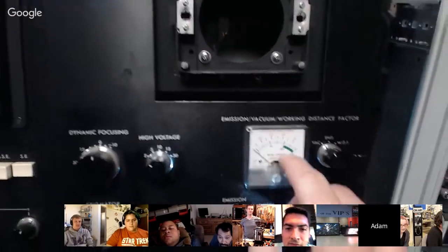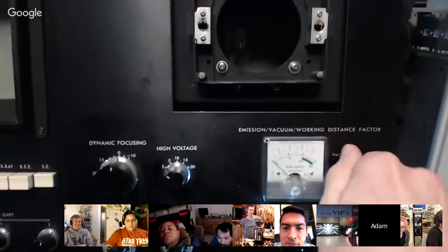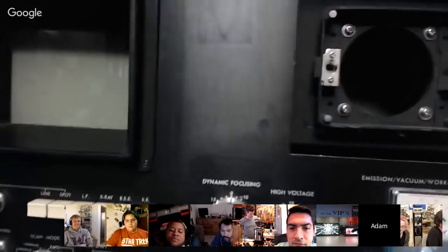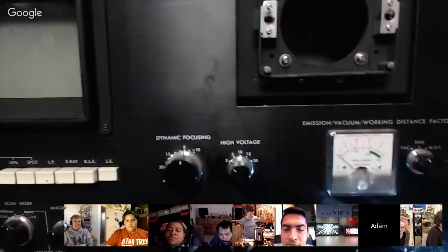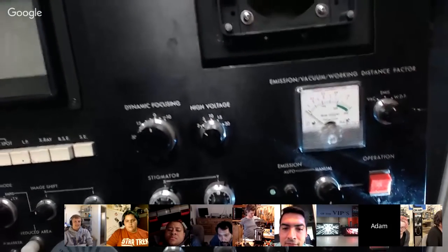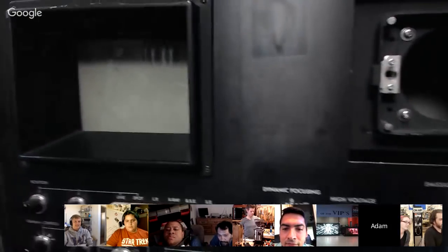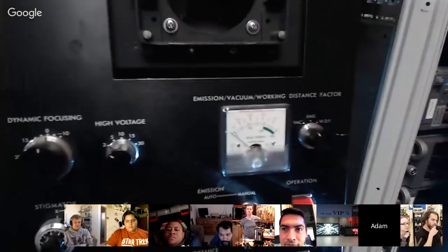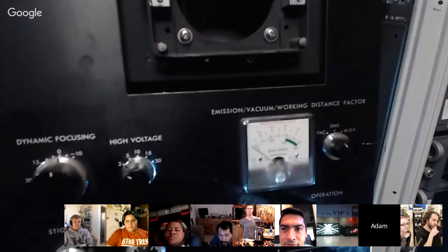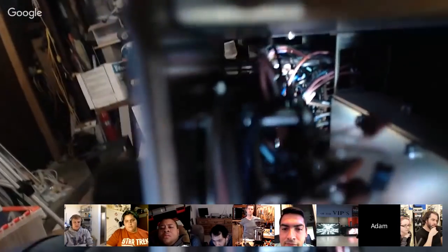The issue is, it's my high vacuum gauge, and it should be reading in the green, and it's pegged below negative. So in any case, either my vacuum pump's not working, and I have that turned off right now because it's really loud, or I have a big leak somewhere. And to find a leak, you need to be able to see small movements in the gauge, which you can't do if it's pegged at zero. So I found out that there are two test points on the back of one of the rotary dials that I can tap into.